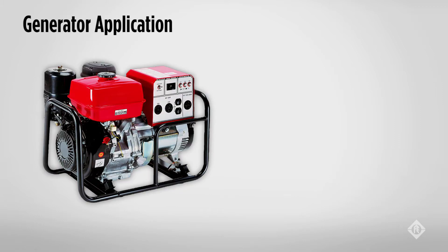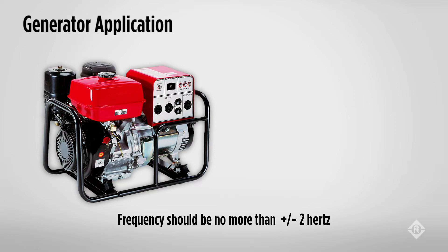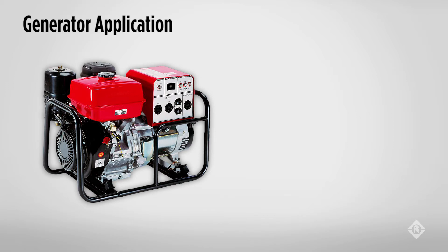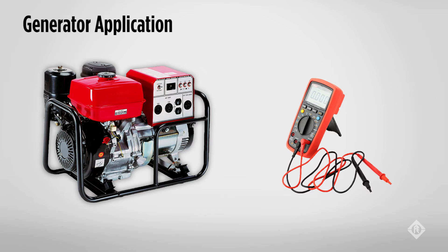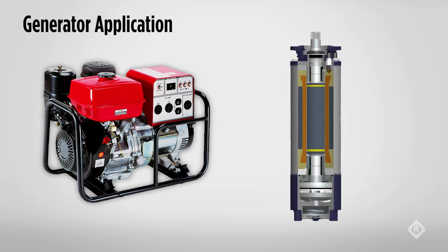The frequency of the delivered voltage will be a function of the generator engine's RPM. If the motor is running slower, output frequency could be a few hertz below 60. The frequency should be no more than plus or minus 2 hertz of 60 hertz. Confirm power frequency with a meter and consult the manufacturer's instructions for adjustment. The thrust bearing in a submersible motor requires a minimum speed of 30 hertz. It is important to start the generator and allow it to stabilize prior to starting the pump motor, and to stop the pump motor prior to shutting down the generator.